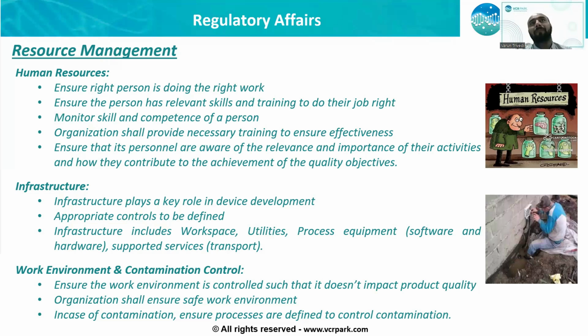Similarly, on transport, many times, especially in cases of IVDs, where there are reagents which are sensitive to temperature and need to be transported from one place to another, we ensure that the overall transporting mechanism is controlled by either putting ice packs or a cold storage environment or any of those. And we also ensure that during the transportation, we have a mechanism to monitor the temperature, because many times if there is a slight fluctuation in the overall storage condition, it might have a huge impact on the final performance of the particular reagent. So keeping the product in mind, the required controls shall be defined and the processes shall be defined for the infrastructure as well.